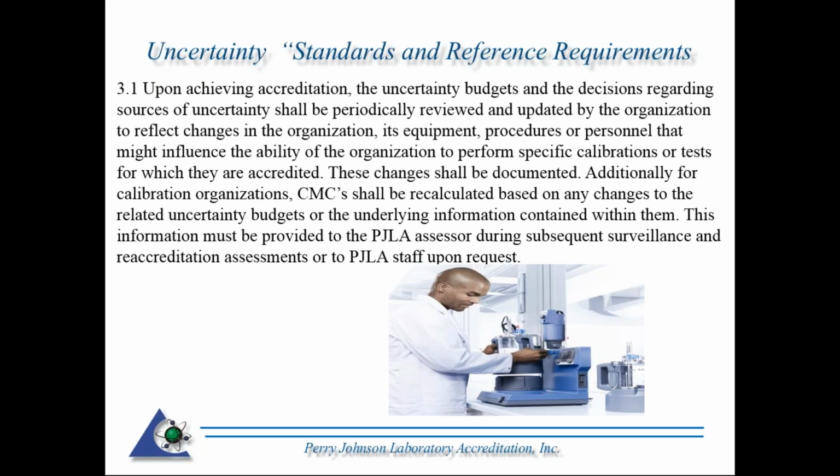These changes shall be documented. Additionally, for calibration organizations, CMC shall be recalculated based on any changes to the related uncertainty budgets or to underlying information contained within them. This information must be provided to the PJLA assessor during subsequent surveillance and reaccreditation assessments or to PJLA staff upon request.